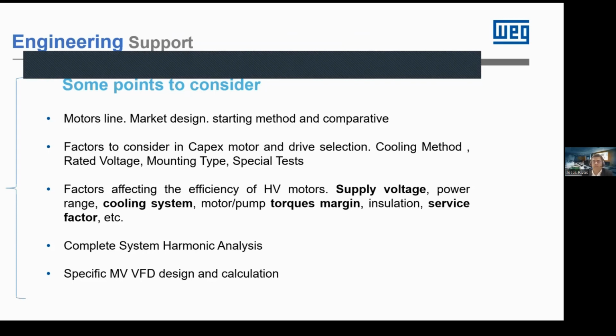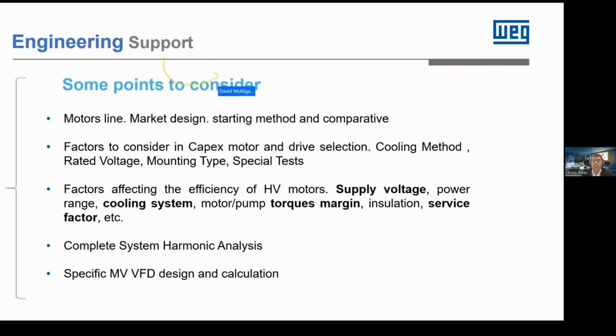Supply voltage, I mentioned that before, safety margins that we are going to consider between the motor and the pump. This is crucial sometimes. The insulation of the motors, what is required, the service factor. So many technical factors, many technical aspects that should be considered. Also, the complete system may have to do a harmonic analysis. You have heard about the total harmonic distortion. We have to design a specific motor and drives and make all these calculations that are more appropriate to the duty point that we are actually going to have in operation.